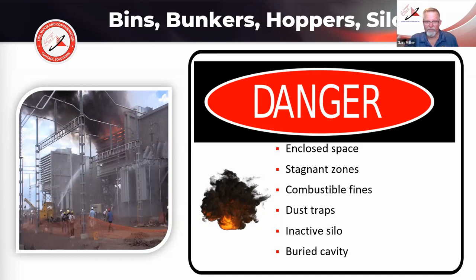Combustible fines tend to float and settle on horizontal surfaces wherever they can find them. Dust traps and inactive silos are another area where, if not cleaned out appropriately, spontaneous combustion can occur. If a crust builds up in the coal in a silo, a cavity can develop or burn out underneath that crust. When the crust collapses, it creates a large puff event of dust, causing a primary explosion, and then all the float dust left around gets aerosolized and causes a secondary explosion that can be much, much larger.